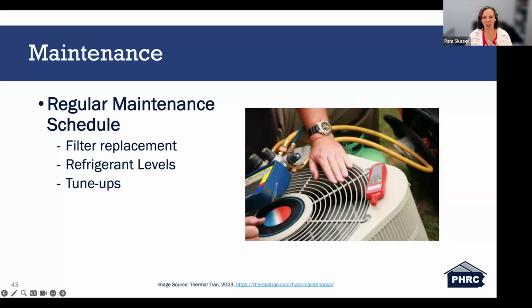Filter replacement. They suggest to replace the filters or check them at least every 1 to 3 months. This is something you could train the homeowner. They can do a little bit of upfront work checking this on their own, but it's essential that at least once a year, there are specifications where they do recommend an HVAC technician should maintain the system every spring and fall, but at least if they're checking it once a year to check for refrigerant levels or any tune-ups, regular cleanings are essential with the system to keep it running properly as well.